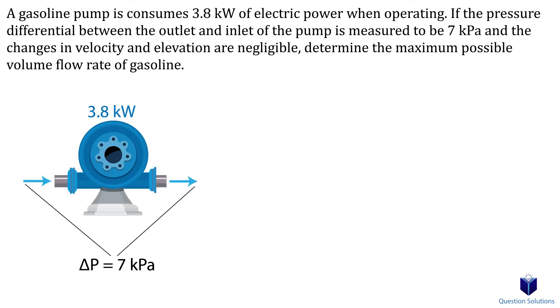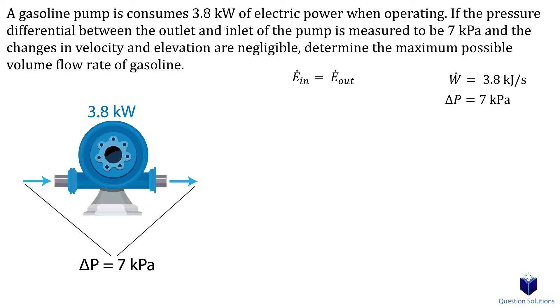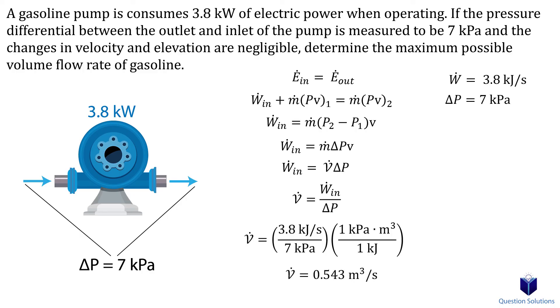Let's take a look at one last example. We have a gasoline pump that uses 3.8 kilowatts of power and creates a pressure difference of 7 kilopascals between the inlet and outlet of the pump. We need to find the maximum possible volume flow rate. The power usage is 3.8 kilowatts or 3.8 kilojoules per second, and delta P is 7 kilopascals. This question is very similar to the previous one. We write our energy equation: power going into the motor plus flow energy in equals flow energy out. Isolating and substituting mass flow times specific volume as volume flow, then applying the unity conversion ratio, gives us the maximum possible volume flow rate.